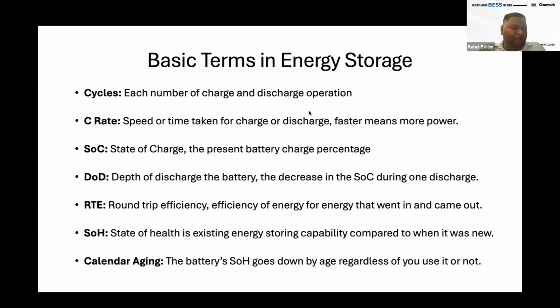Calendar aging is reduction of health because of not being in use. So you use it and there's some reduction in health, as well as when you don't use it, due to the time factor and the storage - the SOC it's in, the temperature it's stored in, and the time it's stored for. All this also causes degradation, so we call that calendar aging. It applies to all kinds of batteries, not only lithium or LFP.